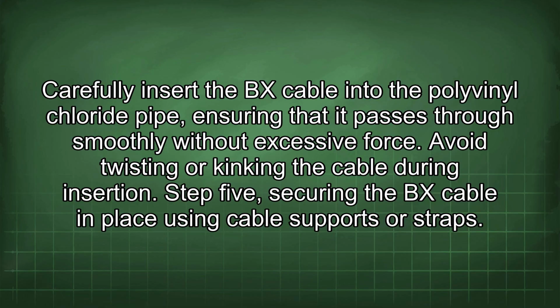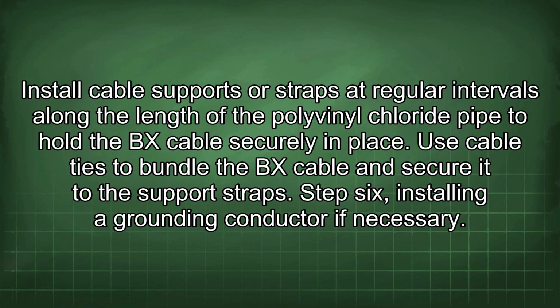Step 5. Securing the BX cable in place using cable supports or straps. Install cable supports or straps at regular intervals along the length of the polyvinyl chloride pipe to hold the BX cable securely in place. Use cable ties to bundle the BX cable and secure it to the support straps.